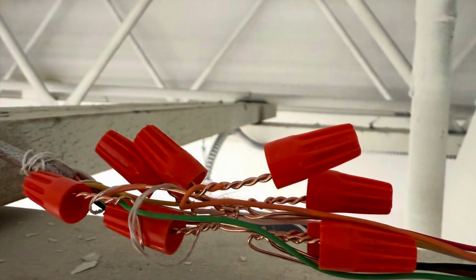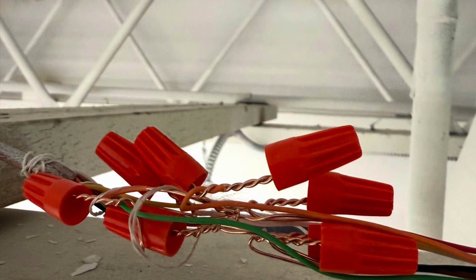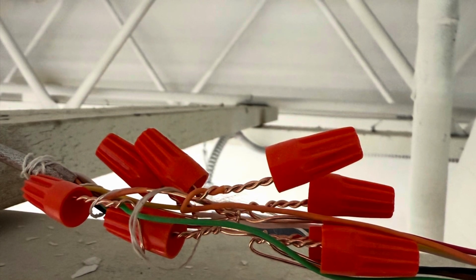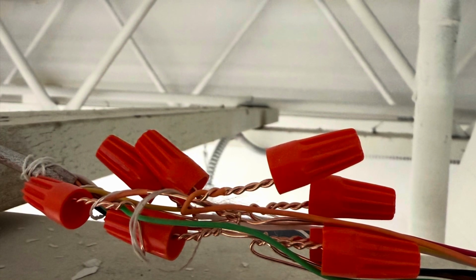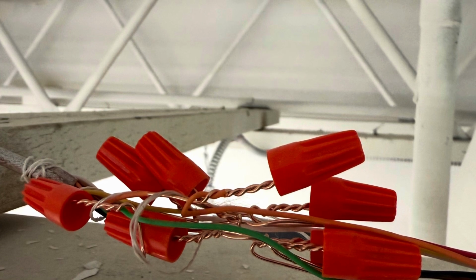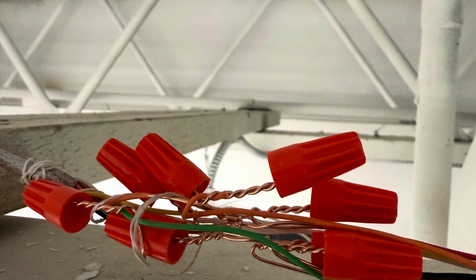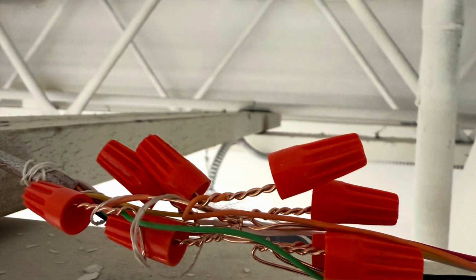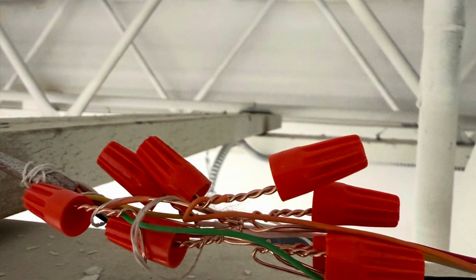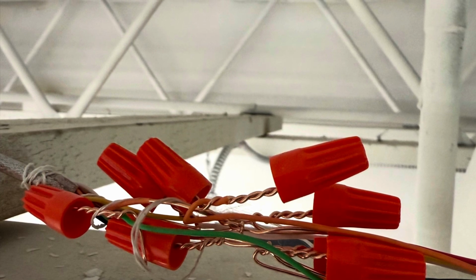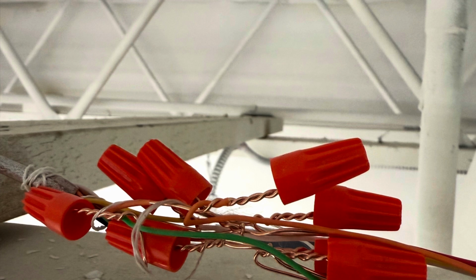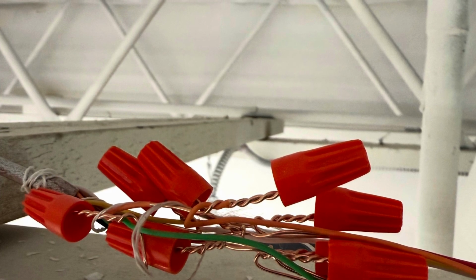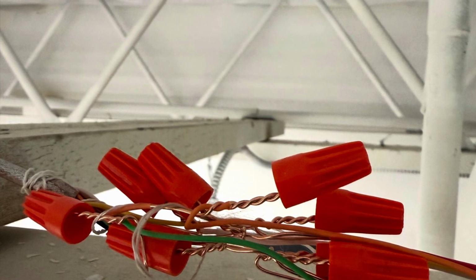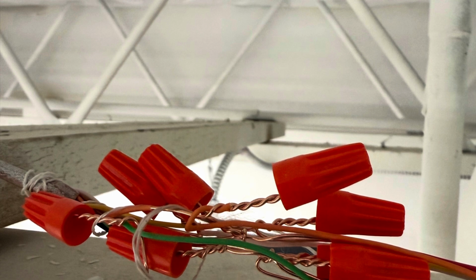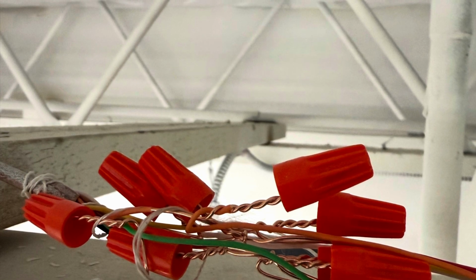All right, guys, so in finding out the short, this is the actual culprit. It was a splice that was made because some of the thermostat wiring was either nicked or was too short. I'm not too sure, but the problem here obviously is super apparent. We have a lot of strip wire, copper against each other. Definitely not a good splice. You want to cut back and only do the copper inside the wire nut and not tape everything together.